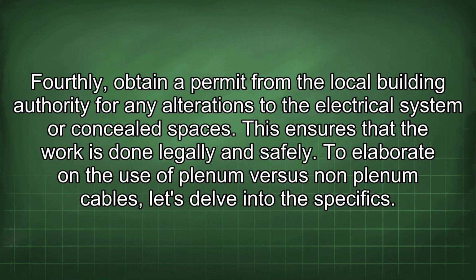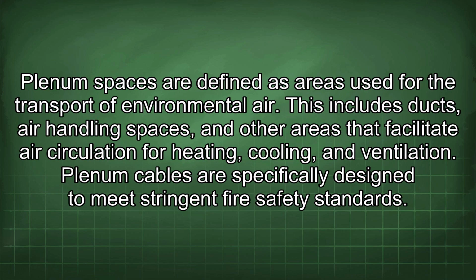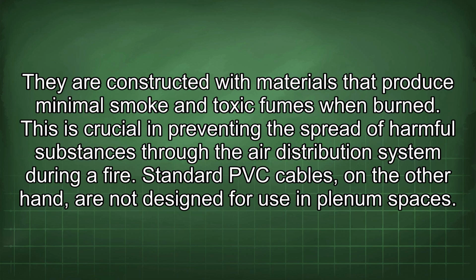To elaborate on the use of plenum versus non-plenum cables, let's delve into the specifics. Plenum spaces are defined as areas used for the transport of environmental air. This includes ducts, air handling spaces, and other areas that facilitate air circulation for heating, cooling, and ventilation. Plenum cables are specifically designed to meet stringent fire safety standards. They are constructed with materials that produce minimal smoke and toxic fumes when burned. This is crucial in preventing the spread of harmful substances through the air distribution system during a fire.